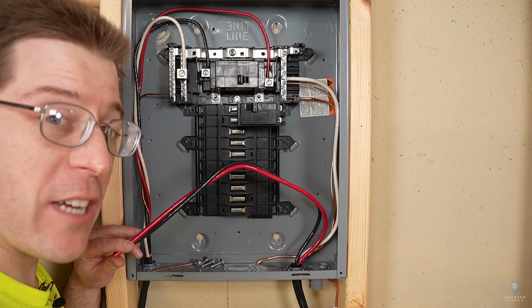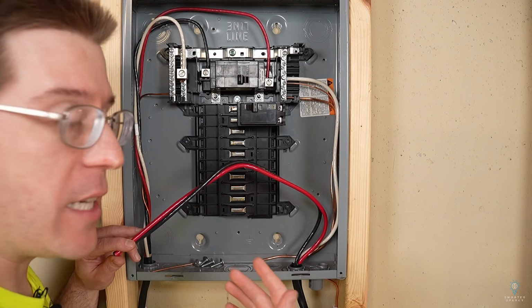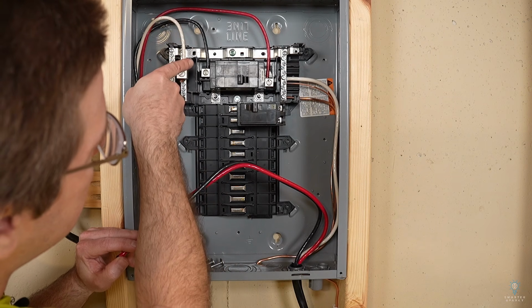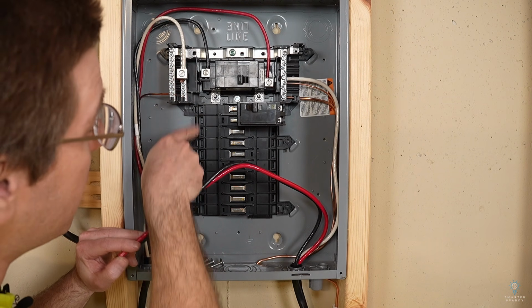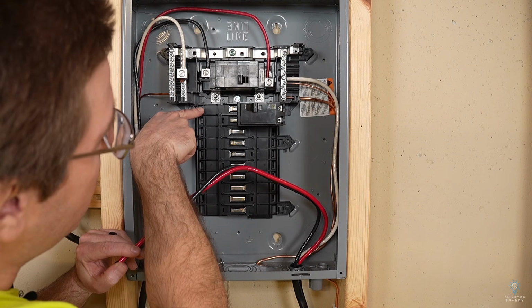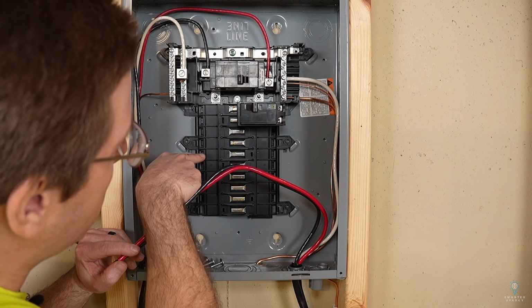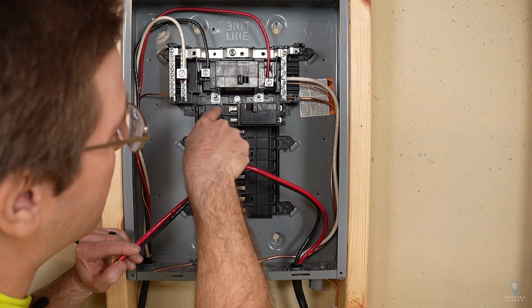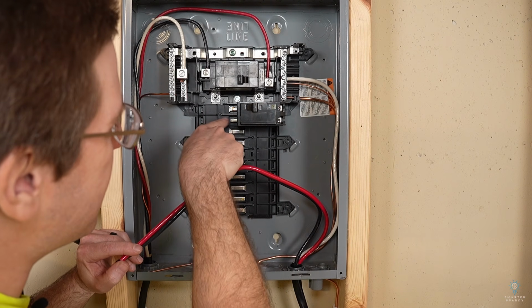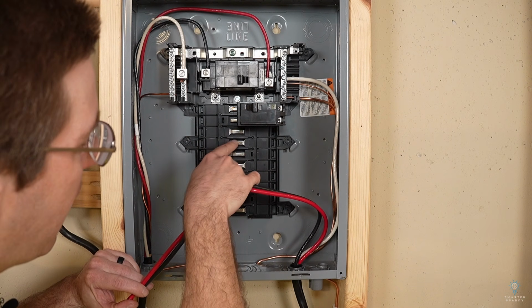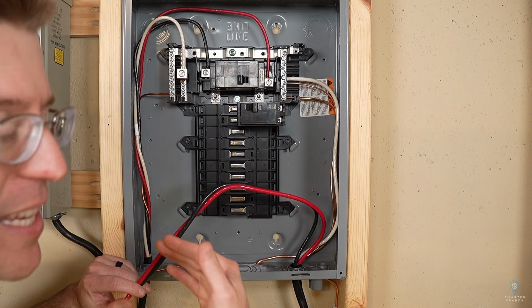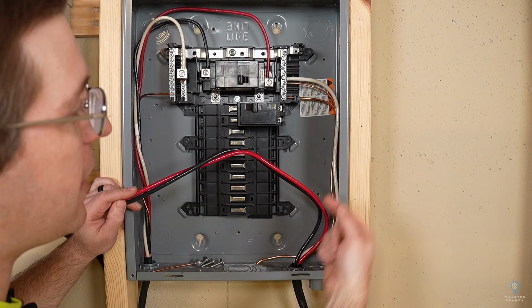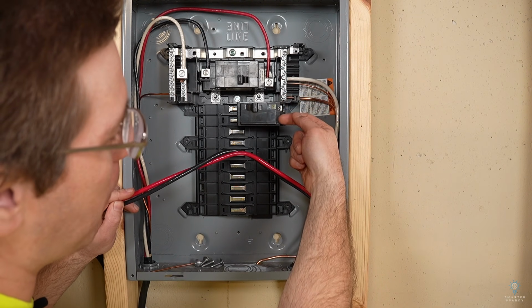If you're doing this professionally, you wanna stick with phasing colors. Because line 1 comes in on the black wire here, it feeds this bus bar, which feeds every other breaker. That means this top row is gonna be the black conductor. This second row is the red, then black, red, black, red, black, red, etc. So if we wanna do it correctly, we wanna make sure black is on top and red is on the bottom.